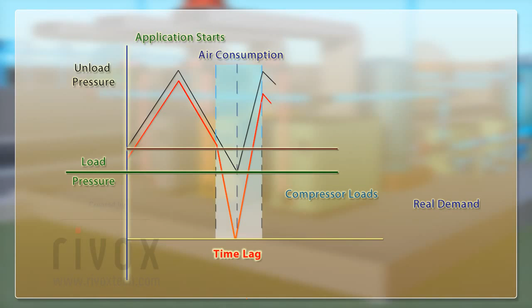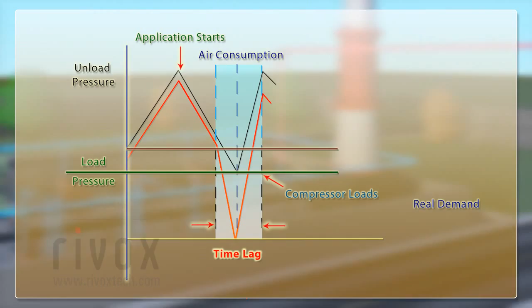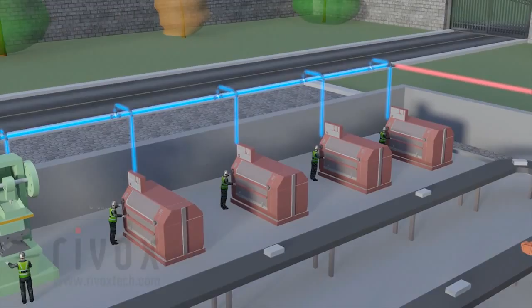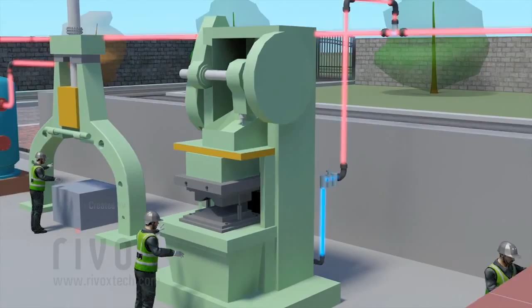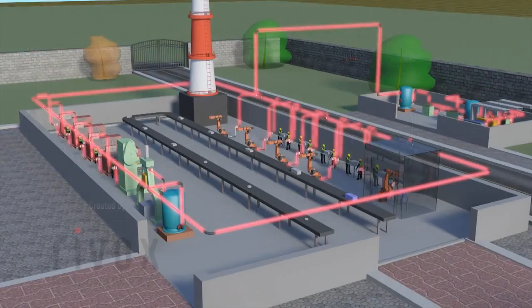Evaluating the above occurrence, what can we conclude? The time taken by the pressure drop signal to reach the compressor and the compressor supplying additional air is larger than the cycle time of the end-use application. By the time the compressor pumps in the required quantity of compressed air into the system, the application has already been completed. Even after the end-use application is completed, the compressor would keep supplying air until it satisfies the set pressure limit. As the system operates at air pressure even marginally higher than required, more quantity of air is consumed by the pneumatic tool. As can be seen, the compressors operate to meet the speculative demand, which can also be termed as artificial demand. When a pneumatic tool is supplied with air at pressure higher than it needs, it consumes more air than it should. This excess amount of air consumed by the application is called artificial demand.